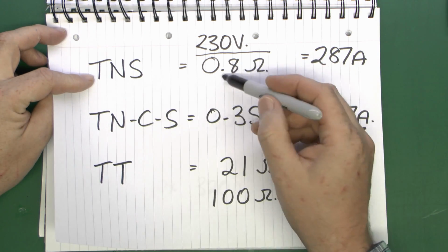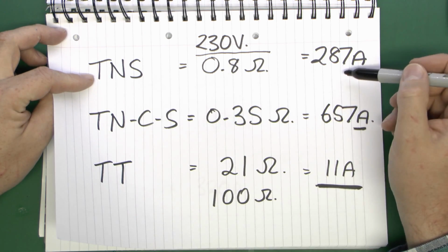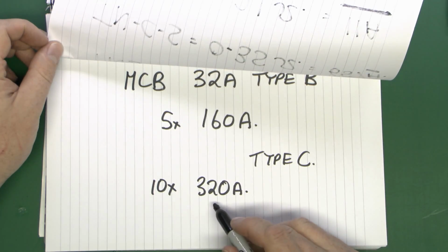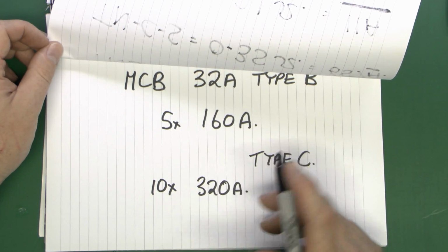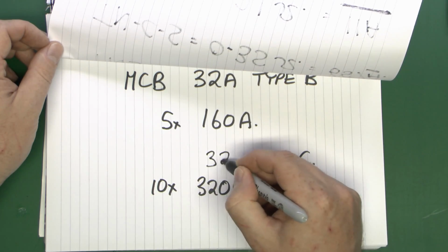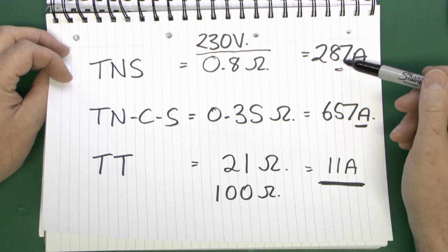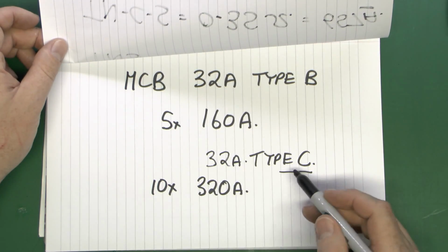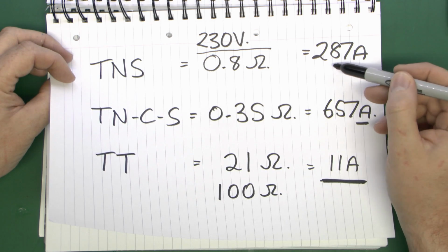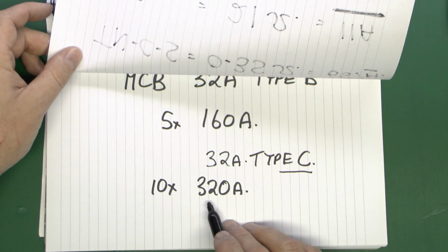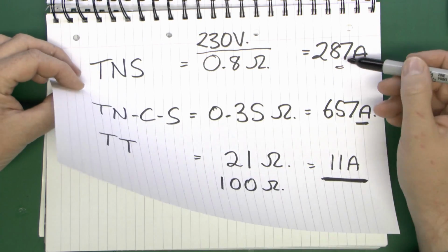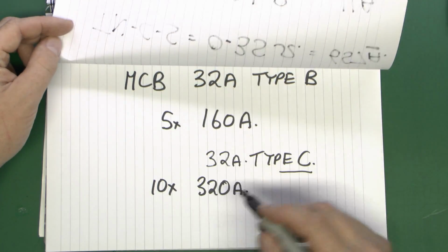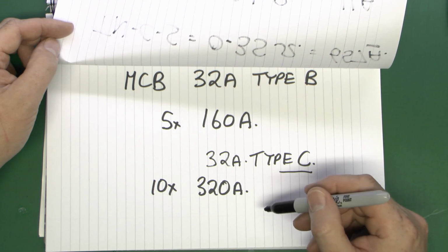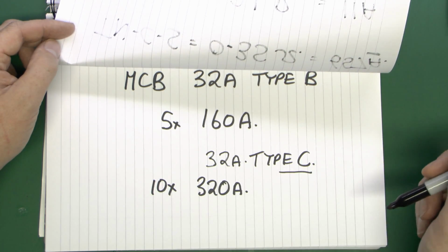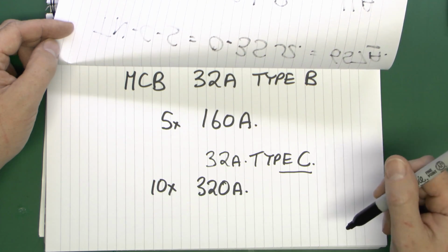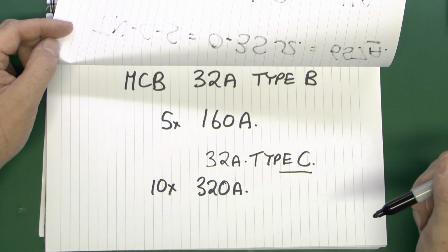But on the TNS supply with the impedance of 0.8, you're only going to get about 287 amps, which as you see there is considerably less than the 320 needed to trip the 32 amp type C reliably. So in this case, you wouldn't actually be able to use a 32 amp type C on this type of supply, simply the fact that the fault current is not large enough to actually trip the device reliably. If you put 287 amps through there, it'll probably trip, but it's going to take somewhat longer, and therefore the tripping time is likely to be more than the required minimum. Typical is around 0.4 seconds, can be larger in some cases.